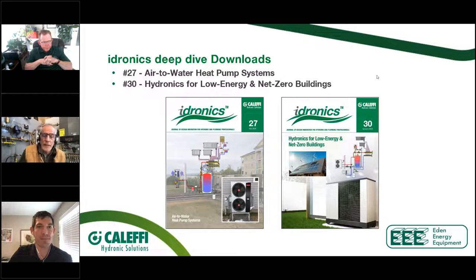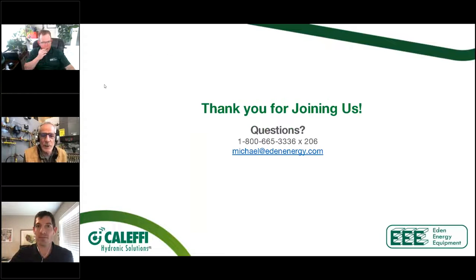How about you, Bob? Yeah, I mean, if you're going to buy high efficiency equipment, make sure you're piping it and controlling it so it can be high efficiency equipment. To run anything, a boiler or heat pump, out of its comfort zone, so to speak, you're not selling that customer what you promised them is high efficiency, which, like I said earlier, the cost of gas isn't going to go down. So whatever the equipment is, you want to use it to the best of its ability. So it's the design, it's the installation, it's the pipe sizing, it's the control, everything has to be looked at as a big picture. For every job, you can't rubber stamp these, which is why you saw so many different piping schematics there. You've got to pick the right one for the application.